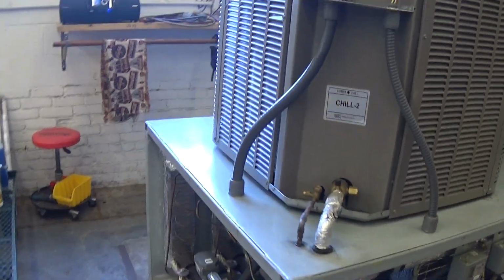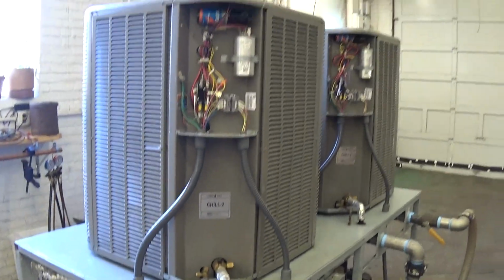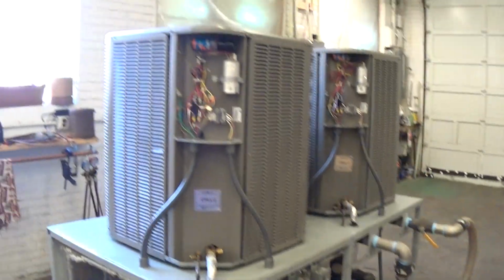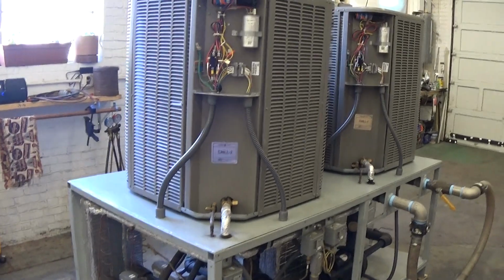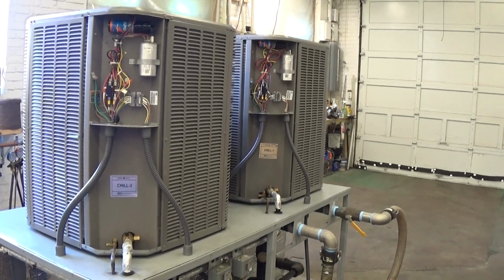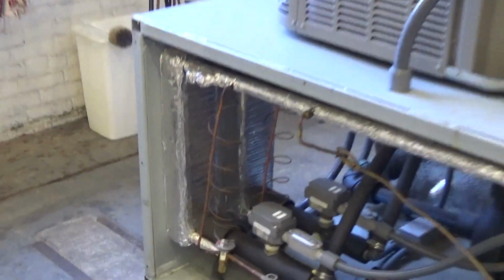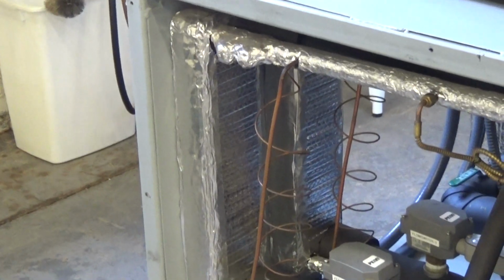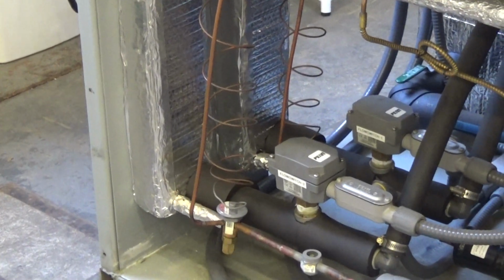This unit is truly a dual circuit chiller. So what does that mean? It means we have the condenser compressors, two completely separate ones on top of the unit. We also have two independent evaporator brazed plate heat exchangers.